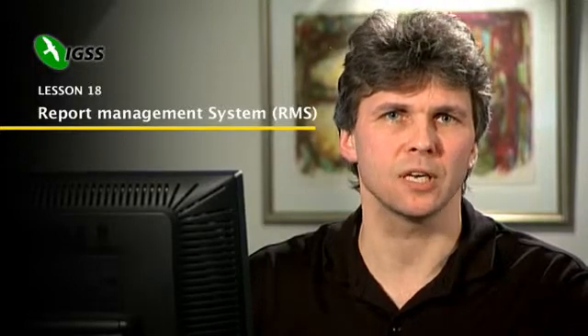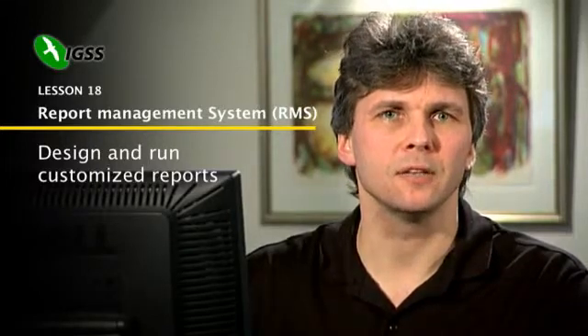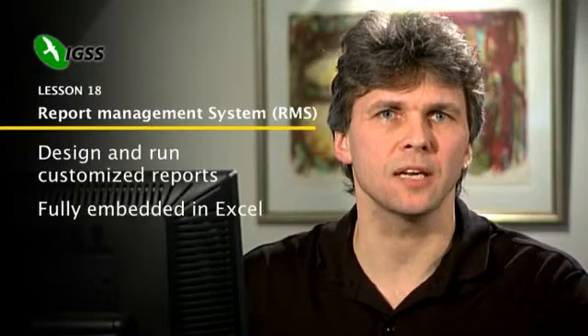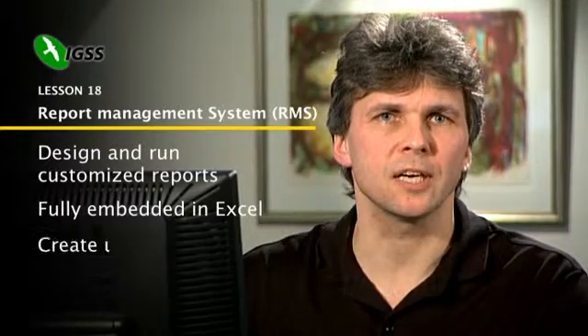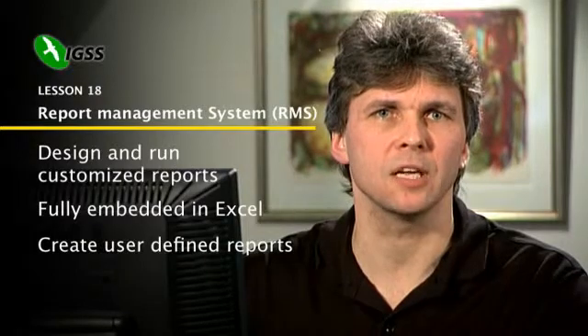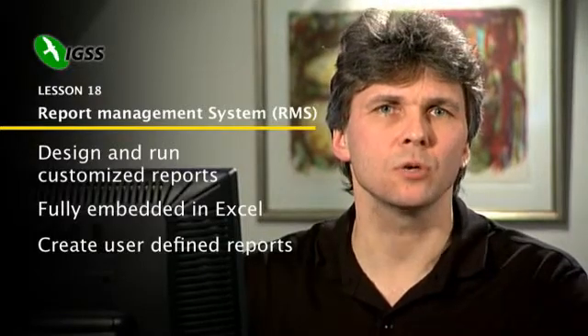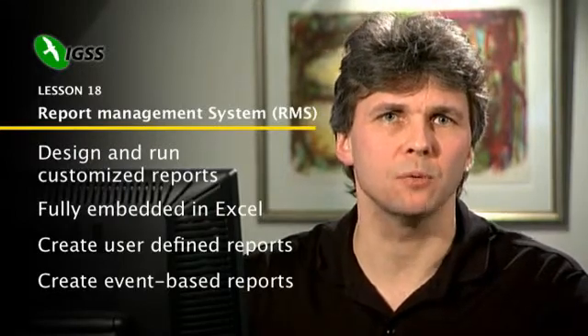The RMS module in IGSS is a module you use for creating customized reports. It is included in the standard version, so it's not an add-on. You can both design and run customized reports from the RMS module, and the RMS functionality is fully embedded in the Excel environment. In RMS, you can design user-defined reports based on log data, BCL data, and hour-day-month values, and you can also create event-based reports, which are typically used for batch reports in production processes.